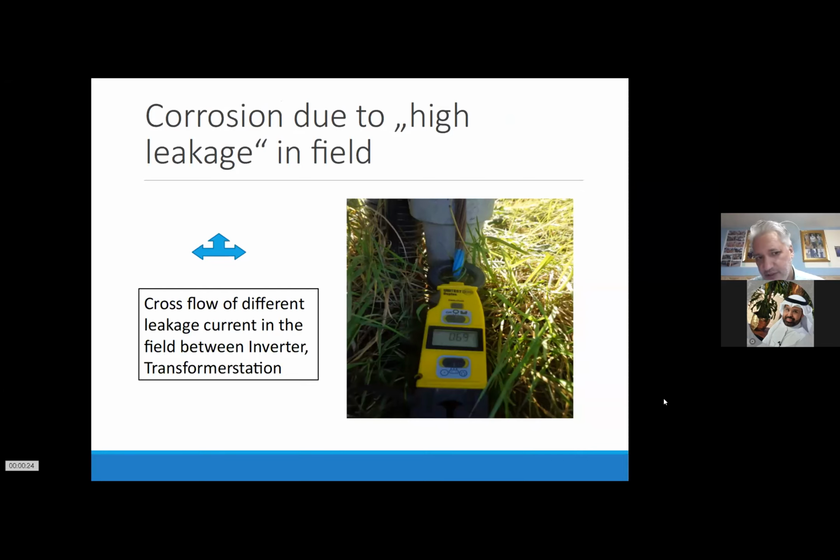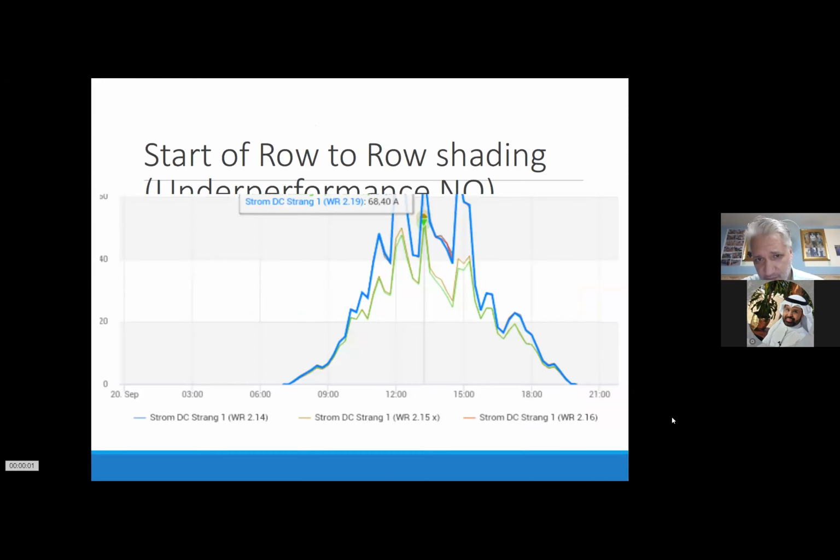That means you have a high possibility of a leakage current because it's already affecting the cabling. And underneath the current clamp meter, there is the plastic going into the soil. So they did install it correctly, but like I said, the high leakage is just way too much.